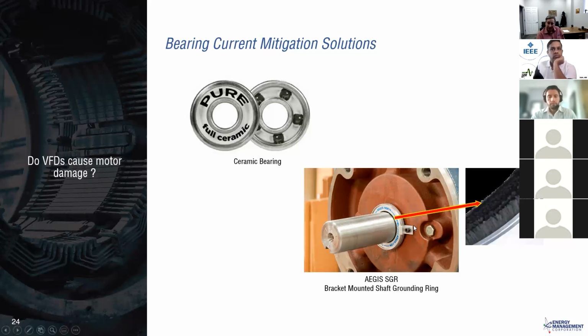But just installing what we call a shaft grounding ring does a really good job, except that when you get into larger machines approaching over 100, and by the time you're at 200, you really have to make sure you're also insulating one end, either with a ceramic bearing or a ceramic coated journal. And in the NEMA MG1, it does talk about even having two insulated bearings. But that shaft current is going to come out somewhere if it doesn't go to ground. So it could come out through your pump bearing or through some other location that's connected to that shaft.